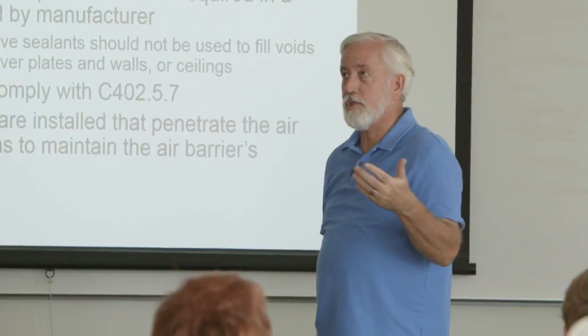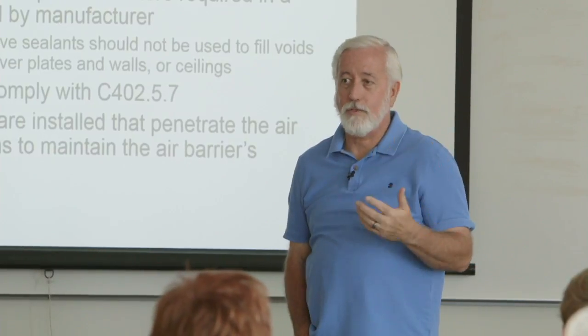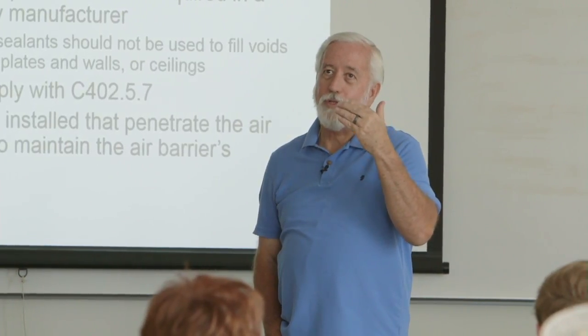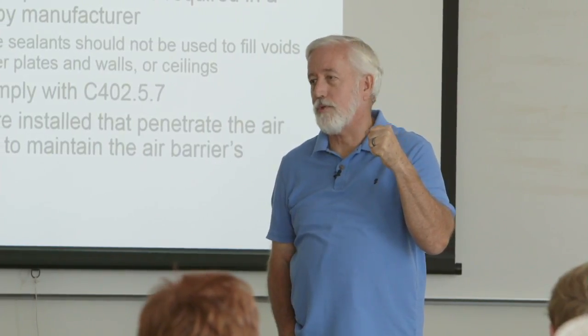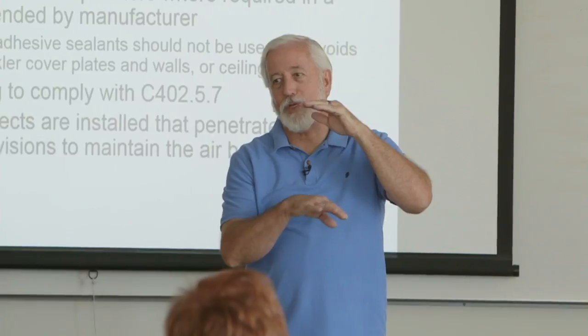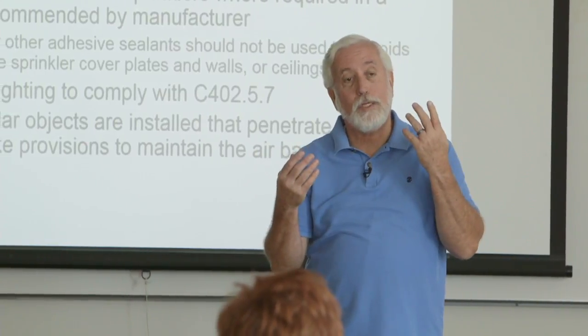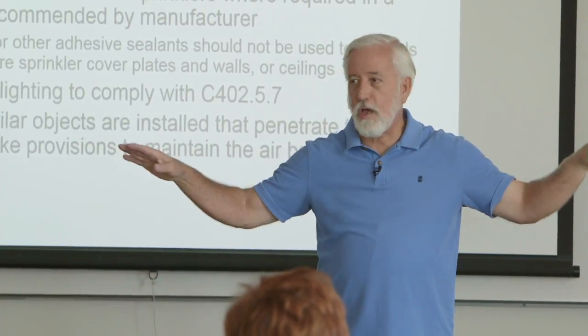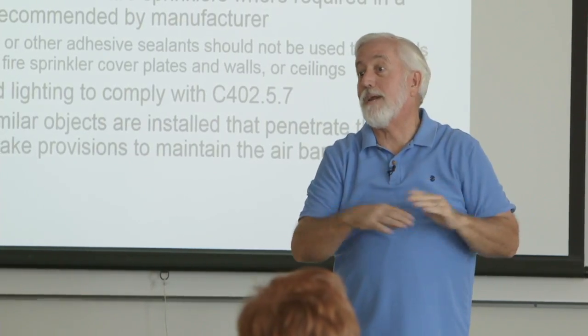When I was doing HVAC, and I did a lot of multifamily, my company probably did 5,000 multifamily units. There was a lot of running around in circles trying to figure out how to install those systems and maintain the integrity of the fire separations at the ceilings. And what really works out best is you go into a unit and you put a lid in it, a drywall lid, and seal it off. You have a fire assembly with the membranes and everything, and it's complete. And then put everything underneath it and drop again.